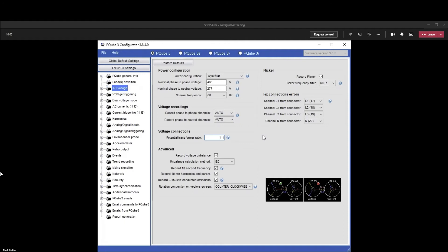For setting the potential transformer, the PT ratio, for example if we're doing a medium voltage circuit where it's 12,470 or 4,160, we would do that ratio of 12,470 in and 120 out, so whatever that ratio is. Leave all this basically the same.